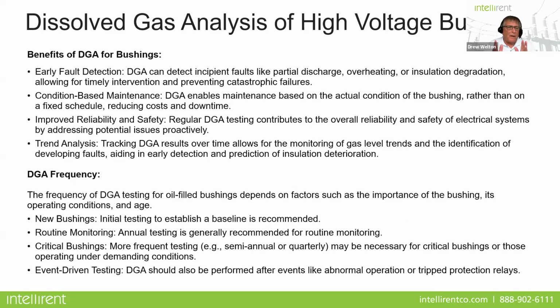There are some benefits to doing a DGA, and that is early fault detection and condition-based maintenance. A DGA enables maintenance based on the actual condition of the bushing rather than a fixed schedule, which could reduce your costs and downtime while improving reliability and safety. Trend analysis for DGA, just like in a transformer, is very important for your bushings. When do you do it?